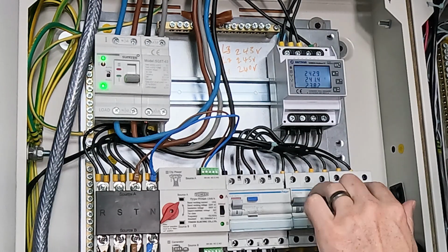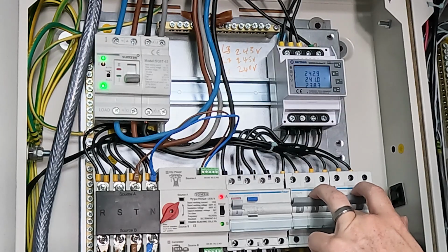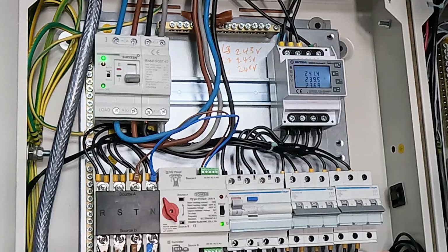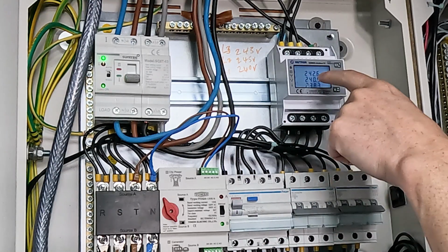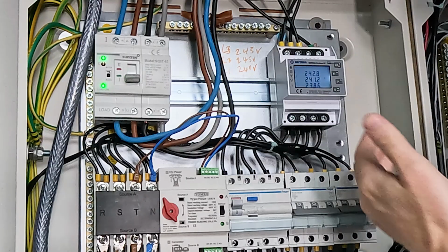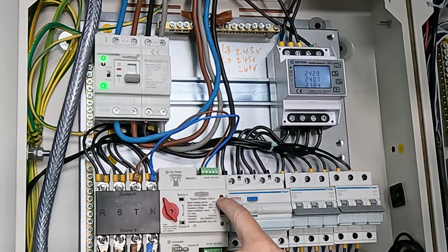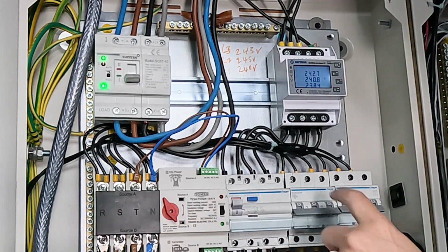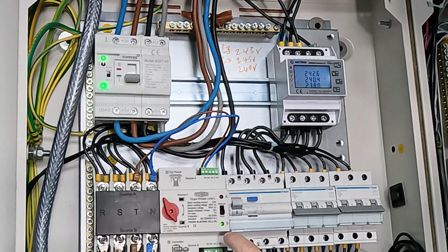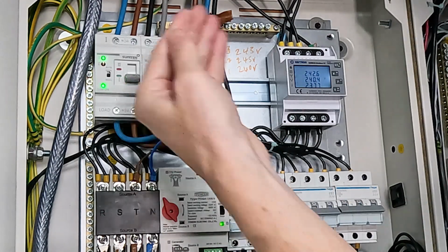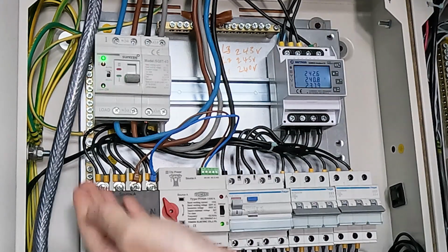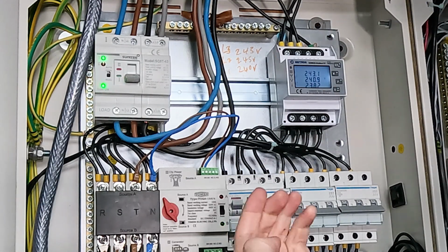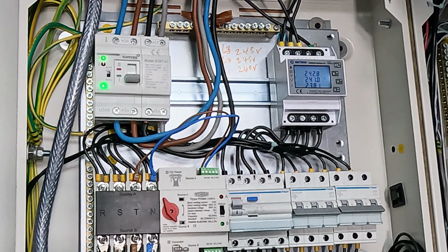So I'm just going to trip my inverters. These are the breakers on the output of my backup, and I trip them, and you can see very, very quickly the meter did not turn off, and there are my grid voltages. You can see that they're 240s, so that is the grid voltages, and there's no voltage for the output of my inverters because I've isolated these, and source B is still live because my main breaker, which is running through to my distribution board and back through to source B, is still on. Very, very nice.